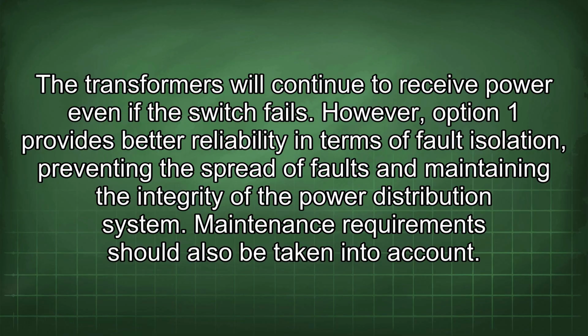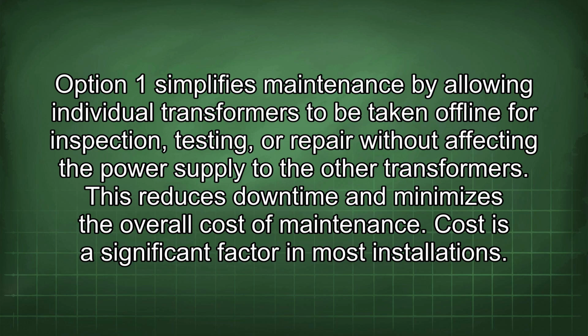Maintenance requirements should also be taken into account. Option 1 simplifies maintenance by allowing individual transformers to be taken offline for inspection, testing, or repair without affecting the power supply to the other transformers. This reduces downtime and minimizes the overall cost of maintenance.